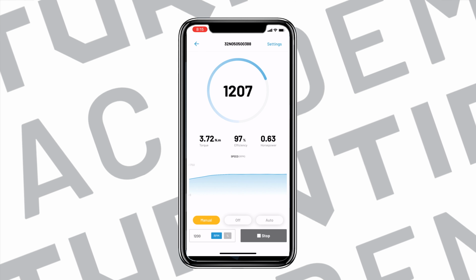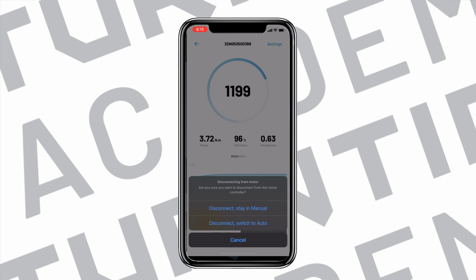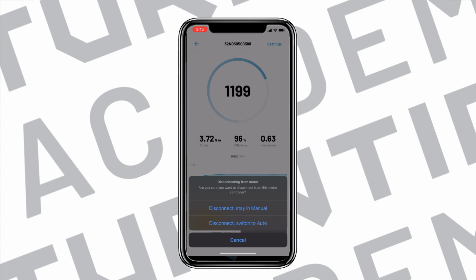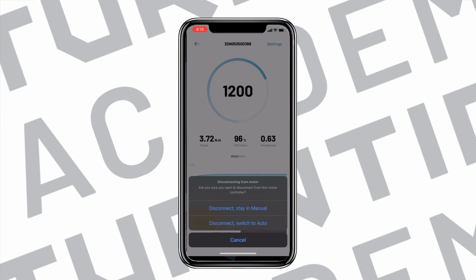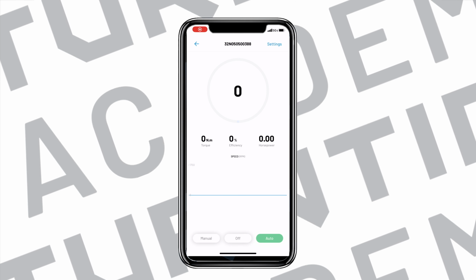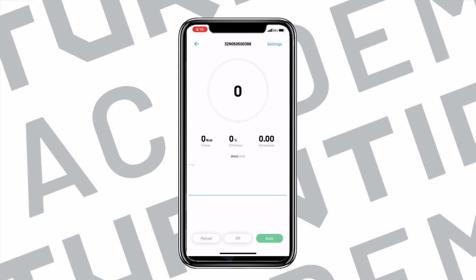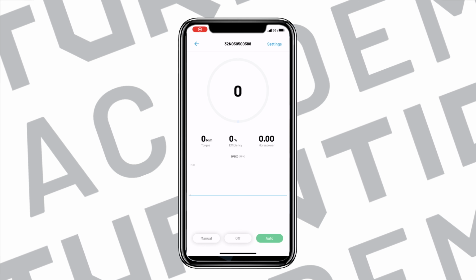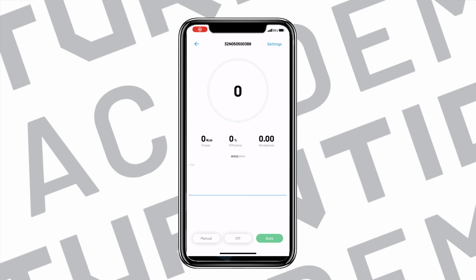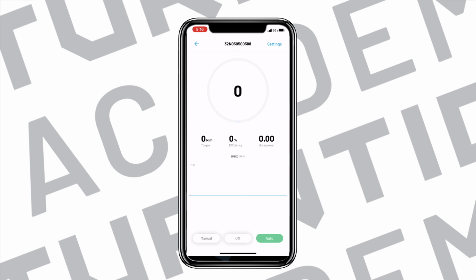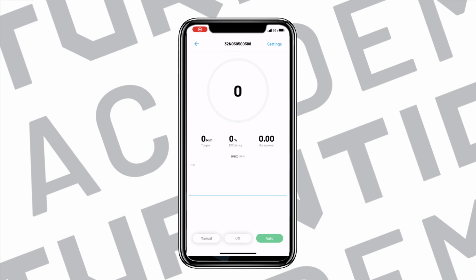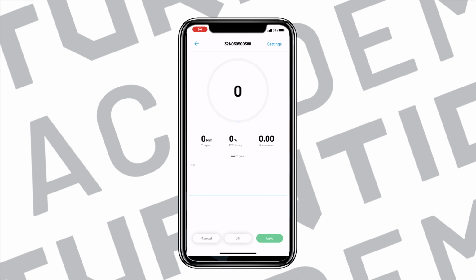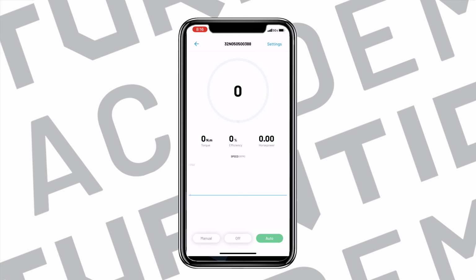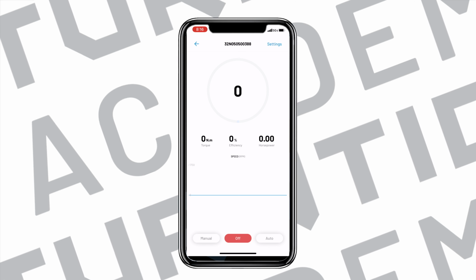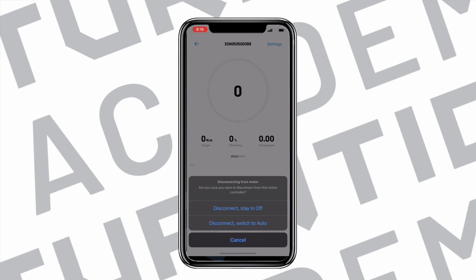If exiting the app while in manual mode, a prompt appears asking the technician if they wish to remain in manual or return to auto mode. The Off selection disables all Turntide motor system operation. This should never be considered a safety device, as RTU electrical circuits remain energized. When off mode is selected, the motor will remain off until placed in manual or auto mode.